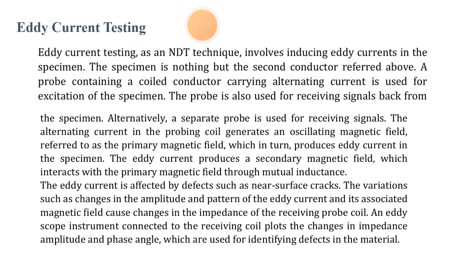The eddy current is affected by defects such as near-surface cracks. Variations in the amplitude and pattern of the eddy current and its associated magnetic field cause changes in the impedance of the receiving probe coil. An eddy scope instrument connected to the receiving coil plots the changes in impedance amplitude and phase angle, which are used for identifying defects in the material.